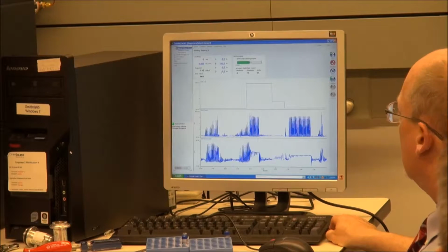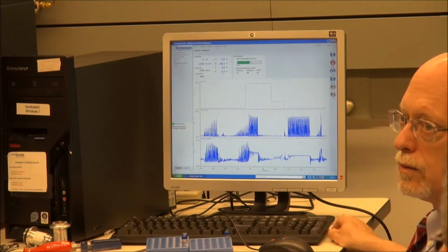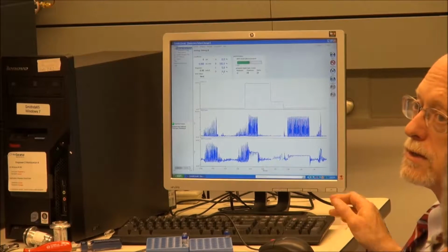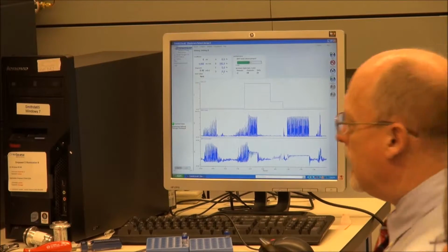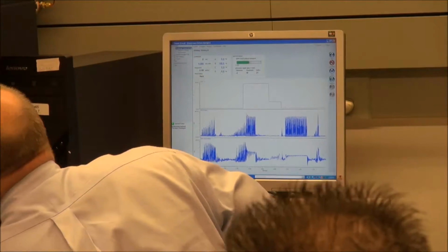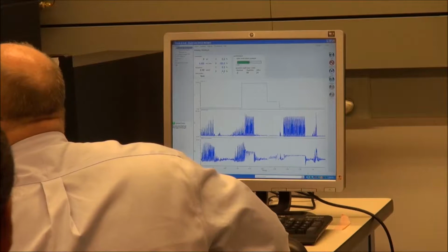I had it in the water. Well, there's tons of air in that line. So what you can do, and you've got to be careful because this is ACN, is you can come up to this line. The A line is primed, the B line's not. So you can loosen it and let it start to siphon, and then tighten it back again.